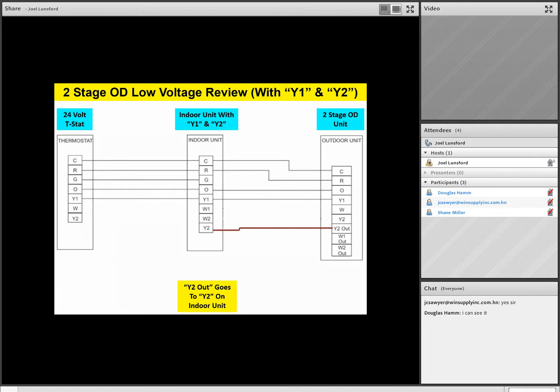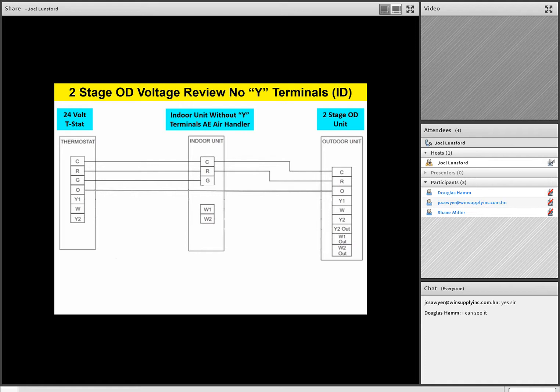Okay. Well, the next little block diagram we're going to look at, we're going to talk about how we may hook up a two-stage outdoor unit if we do not have a Y terminal on the indoor unit. So an example would be like an AE air handler. If you're utilizing the AE air handler, you're going to notice that the air handler doesn't have a Y terminal, doesn't have a yellow wire. So how in the world would we hook that up to where we're going to get normal operation? And again, we'll just use a two-stage outdoor heat pump as an example.